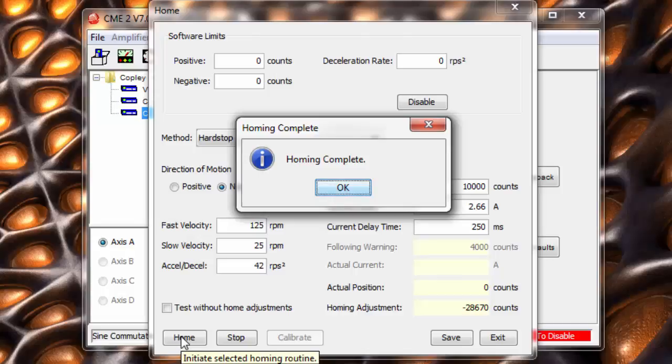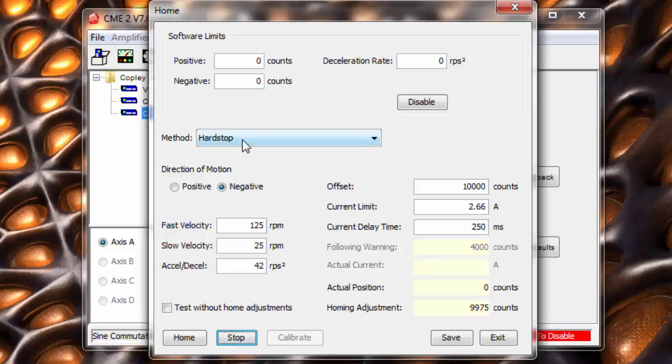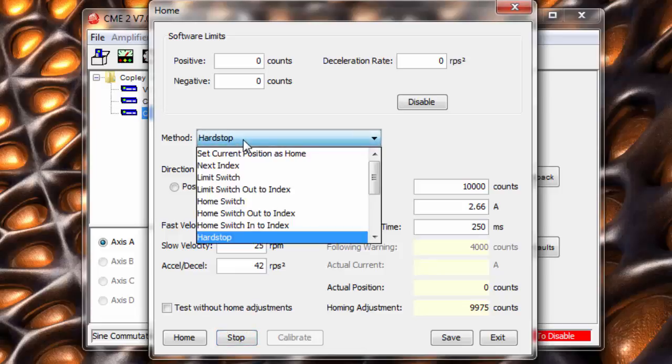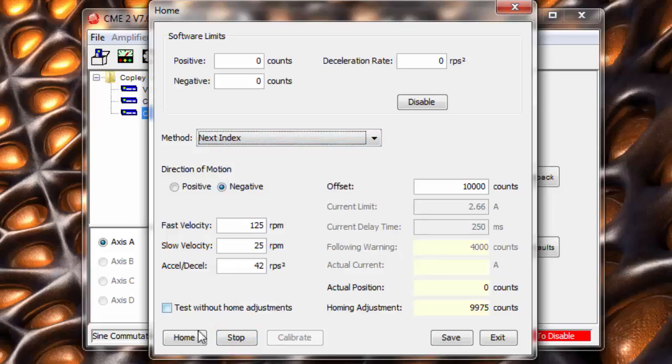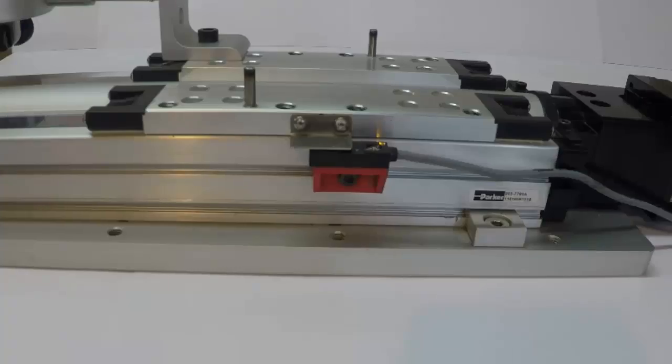A more repeatable homing method is to use the index pulse of the servo. By doing this, the home position will be repeatable within one encoder count of the motor. However, the downside of this method is that we are only homing to the nearest full turn.